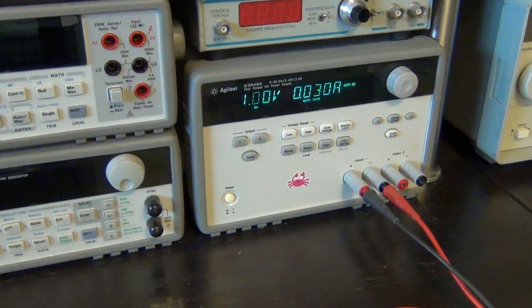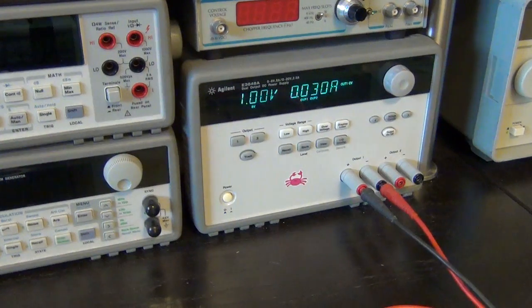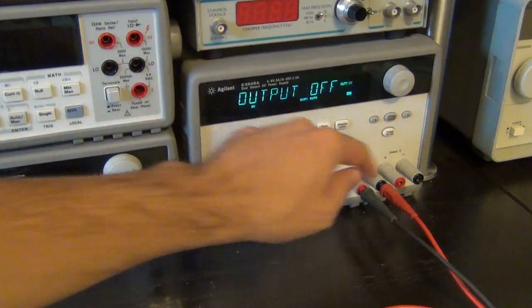And the light that is coming out of the fiber, which I definitely don't recommend you look into because it's infrared, you can't see it. It's around 1,550 nanometer, according to the data sheet. So if I look at the data sheet, it says that the wavelength should be at room temperature somewhere between 1530 to 1563 nanometer. So let's turn the laser off.